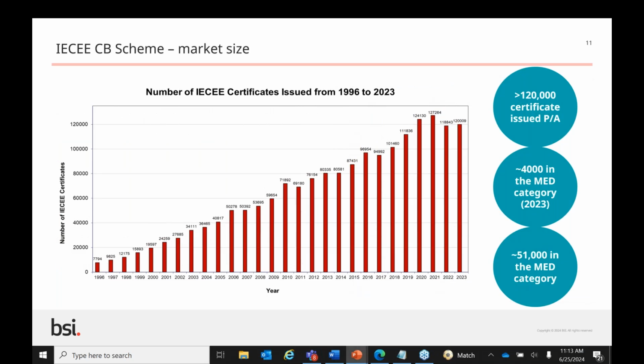And just to show the size and scale of this, here are some statistics for the growth of certificates during the period that the scheme has been operating. This comes from the IEC statistics on their website. There are around 120,000 CB test certificates issued every year. In 2023, there were just under 4,000 issued for electrical medical devices, and over 51,000 certificates have been issued in the med category since 2002. Next slide, please.